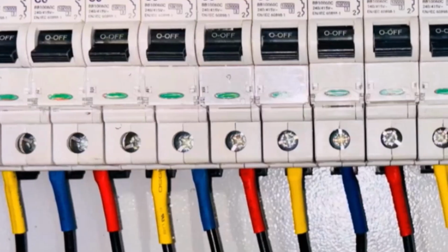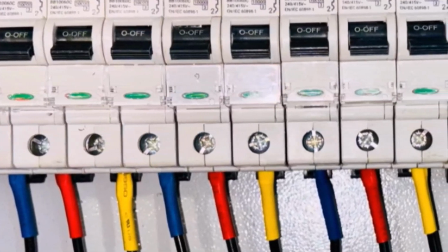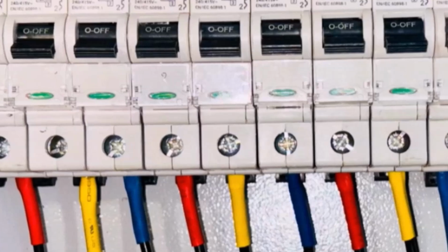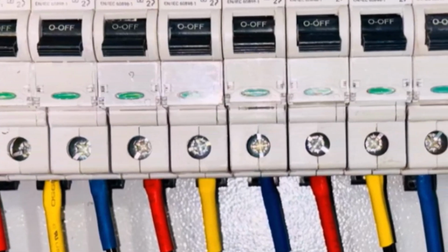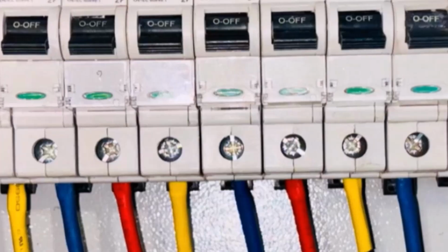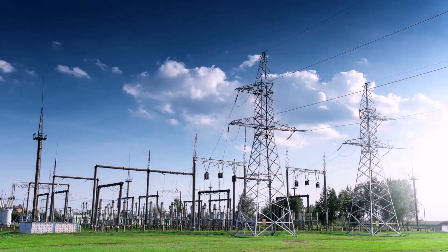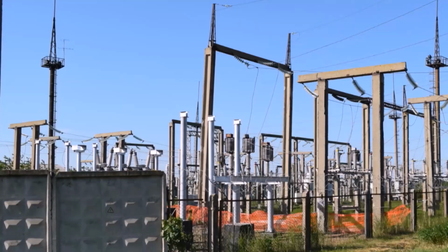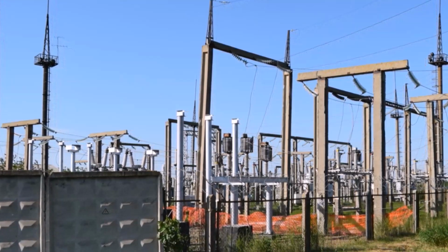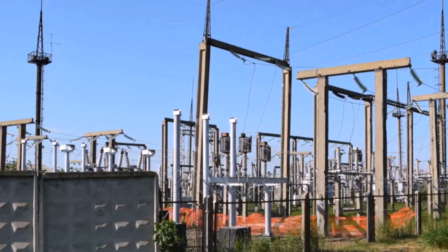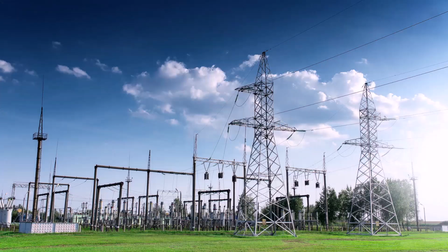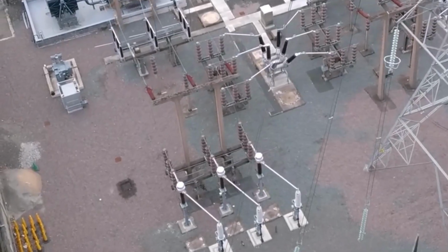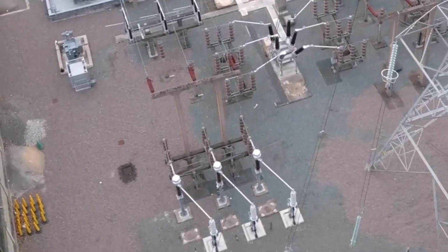For instance, it provides the 120 volts needed for our wall outlets, measured from one line to neutral, and also the 208 or 240 volts needed for larger appliances like ovens and dryers, measured between two lines. This dual voltage capability, originating from a single transformer, is what makes the Y connection the go-to choice for final power distribution, making it both practical and efficient for our daily needs. From the massive generators at power plants to the final transformer on your street, the Y connection is a fundamental building block of our electrical world.